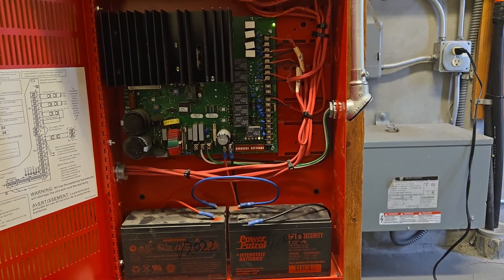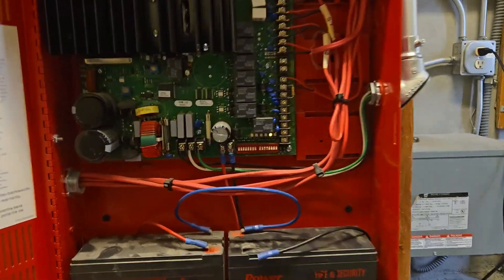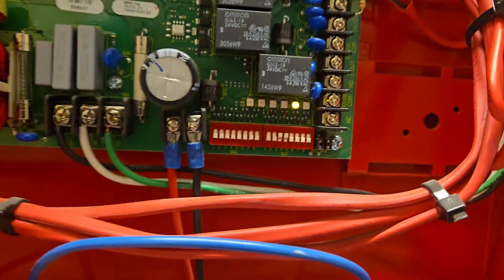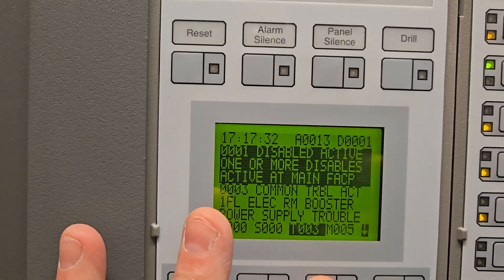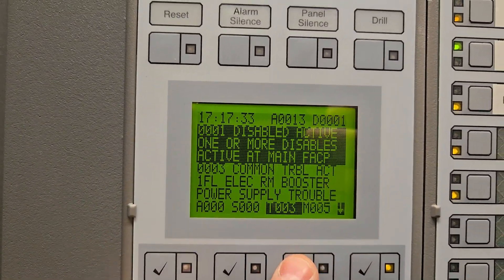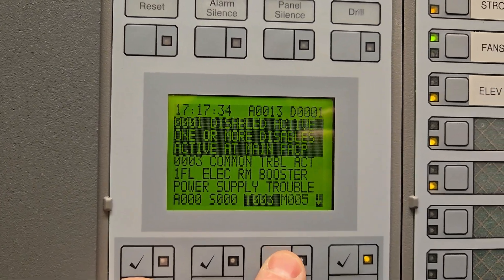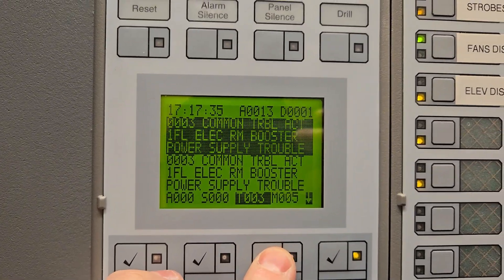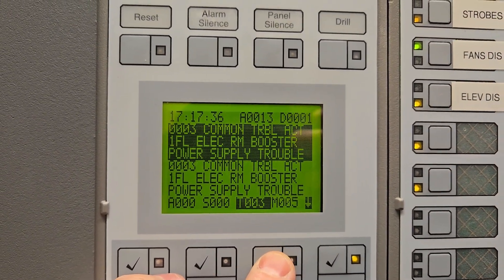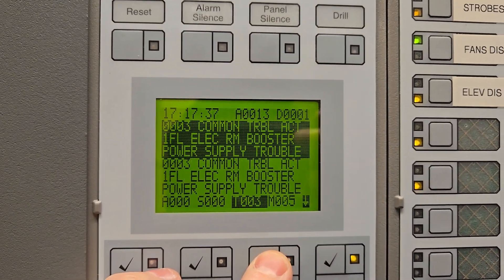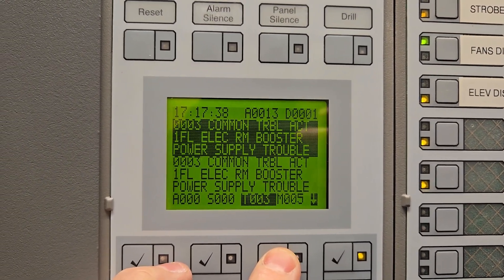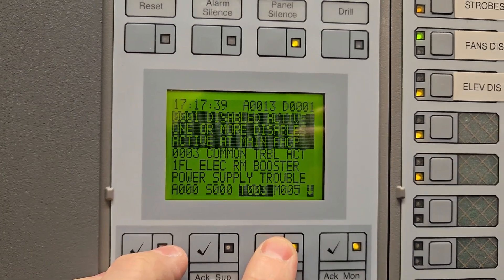You'll hear it click a few times — there we go, we have a trouble light. That just came in. And if we go to our troubles, we will see: first floor electrical room booster power supply trouble.